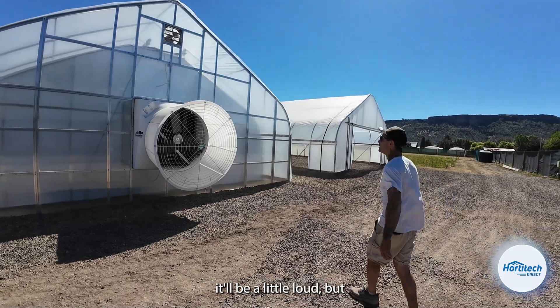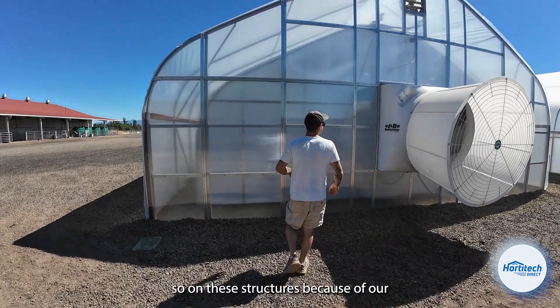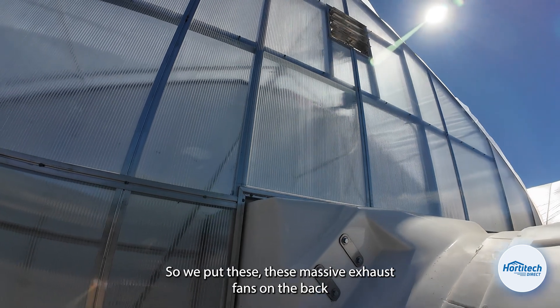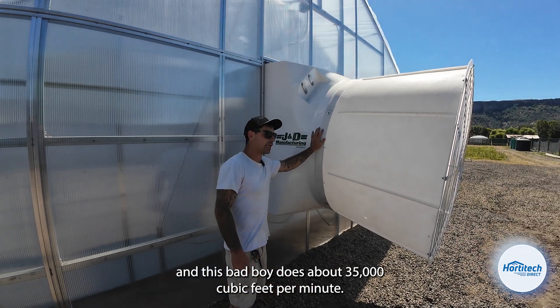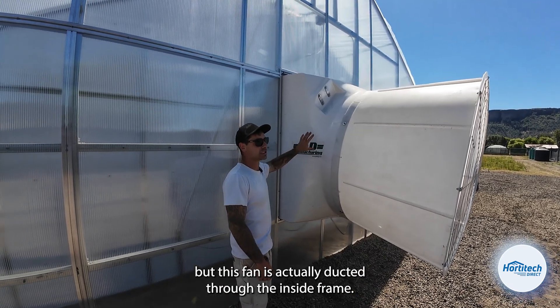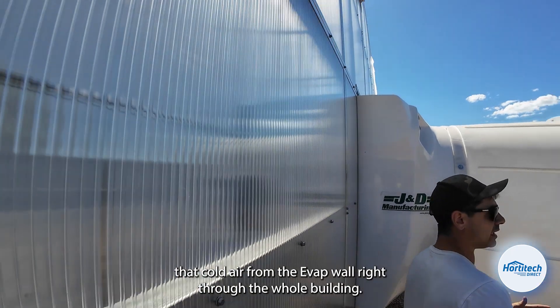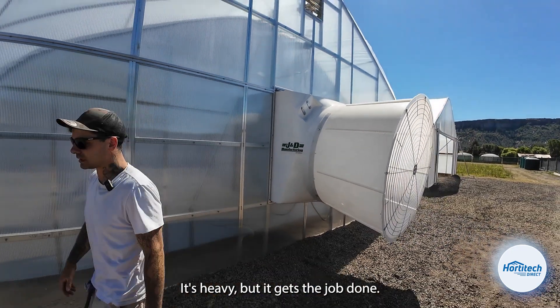This is the exhaust. Because of our motor system between the two structures, we can only put one exhaust fan on these buildings. We put these massive exhaust fans on the back and this bad boy does about 35,000 cubic feet per minute. The fan is actually ducted through the inside frame, really pulling air from that inside frame, through the light trap and exhausting everything out, drawing that cold air from the evap wall right through the whole building. This thing's fantastic — it's heavy, but it gets the job done.